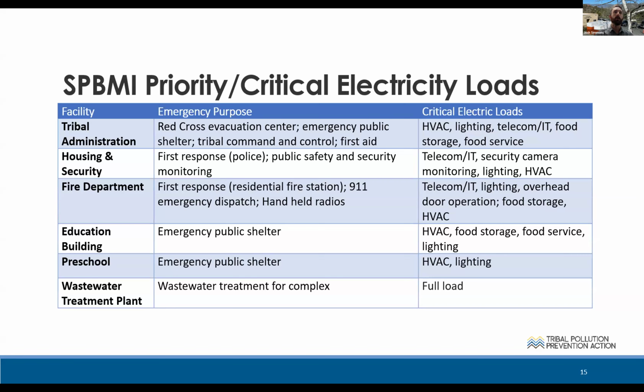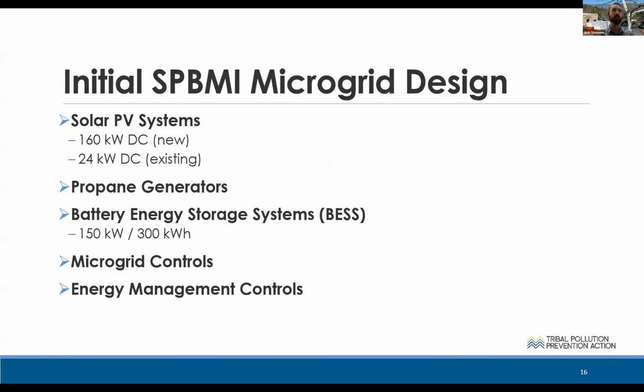At San Pasqual, these were at their government campus. The essential facilities were the admin building, housing and security, fire department, education building, preschool, and wastewater treatment plant, all co-located on the campus, providing essential community services particularly during an emergency. With the information we gathered, we initially sized the solar at 160 kilowatts of new capacity, since there was already 24 kilowatts of existing solar on the education building. There were also existing propane generators, which we were either replacing or supplementing.